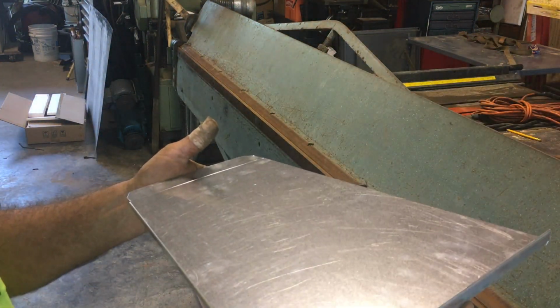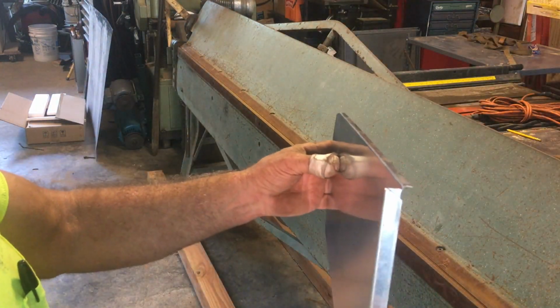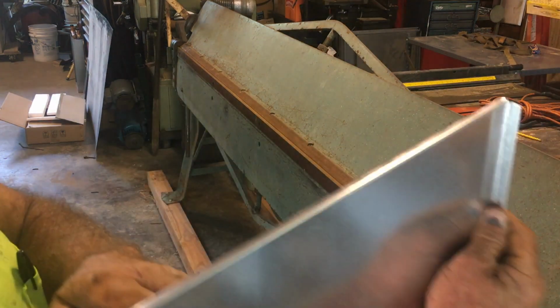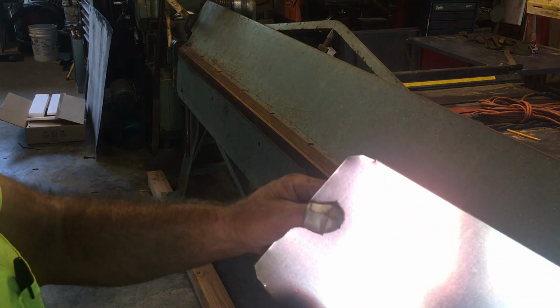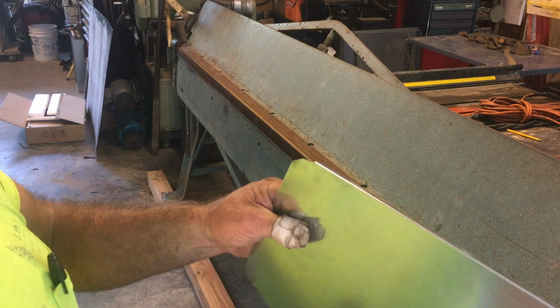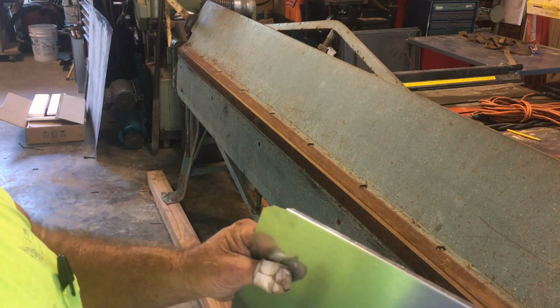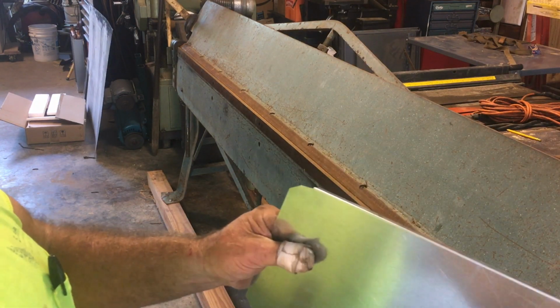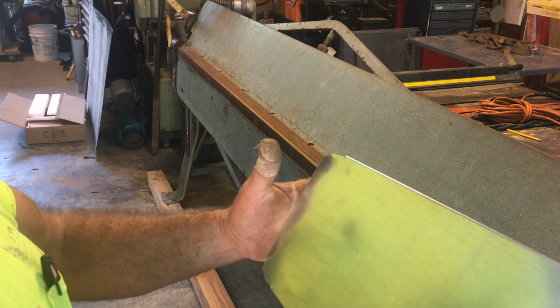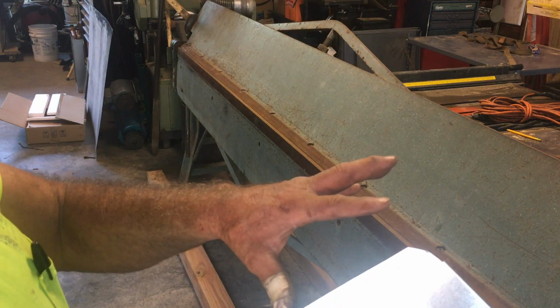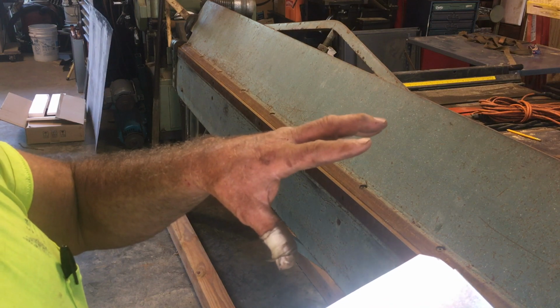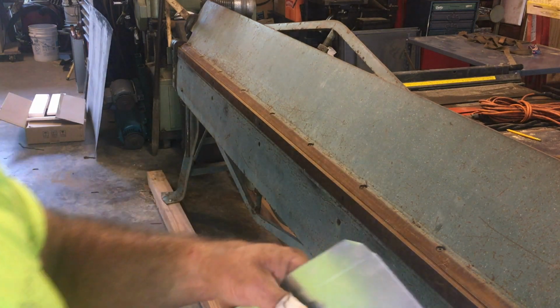That's folded to the outside now. This is going to be the side of the duct, either the left or right side, since it's an equal transition or equal taper. The other dimension is 18 inches up here down to 7.5. This is 12 1/4 to 7.5. We're going to have an end cap on here, and we're going to have that blower attached in the end cap.